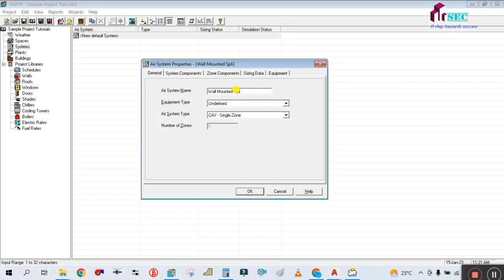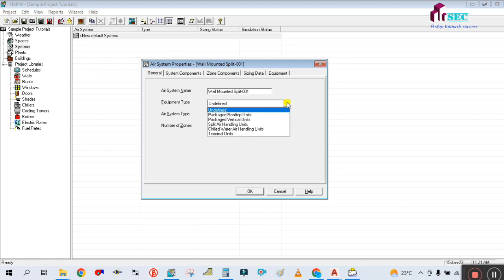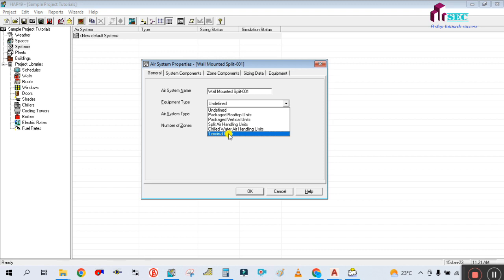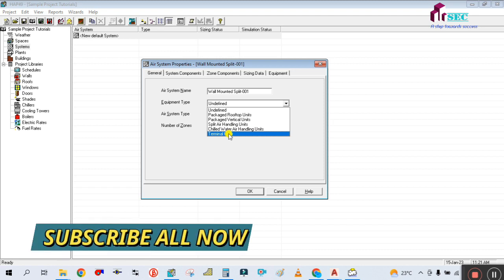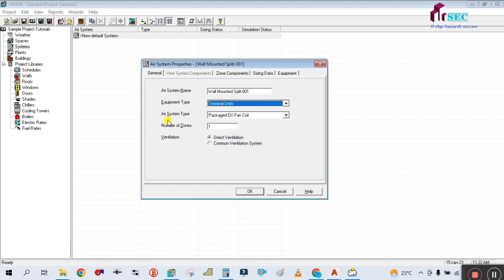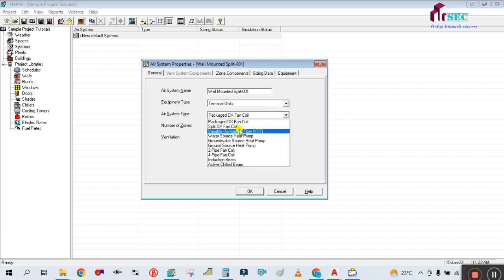For the air system name I am going to write 'Wall Mounted Split.' The air system name will be '001 Wall Mounted Split 001.' Then for equipment type, you have to select for the split unit. There are different types of equipment here: Package Rooftop, Package Vertical, Split Air Handling Unit, Chilled Water Air Handling Unit, and Terminal Unit. For the split system we are selecting Terminal Unit. For air system type, you select Split DX Fan Coil.